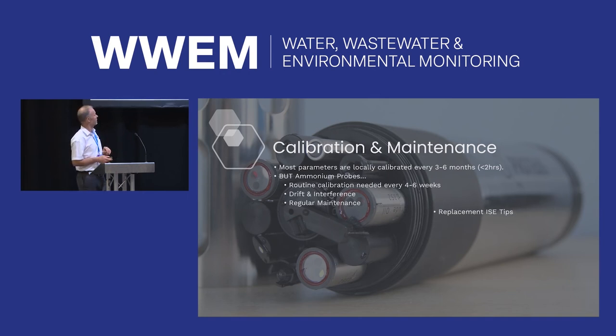They do need regular maintenance, just like kind of every water quality instrument. They also need a replacement ISE tip. That will be done every 6 months, possibly 12 if you're lucky. But the calibration software will usually tell you when you need to do it.